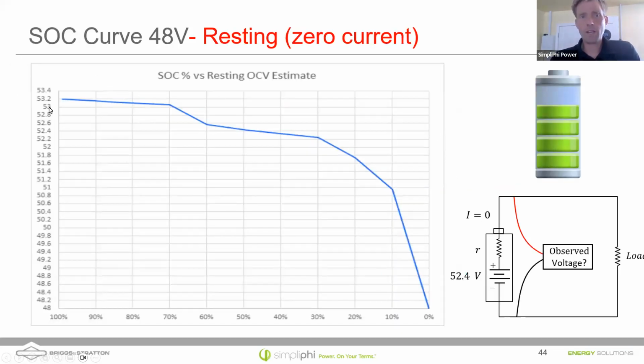So first off, if we look at what the state of charge curve looks like for a resting battery, which has zero current coming in or going out. So you discharge it, you disconnect it, look at its voltage. You discharge it a little more, disconnect it, look at its voltage. And you'll see this voltage start off around 53.2, 53.4 for a fully charged resting battery.